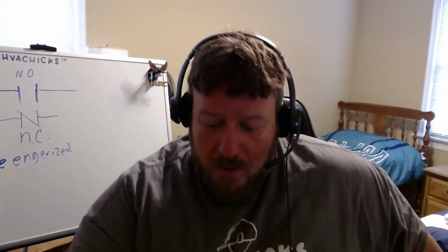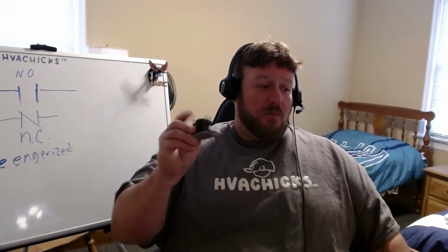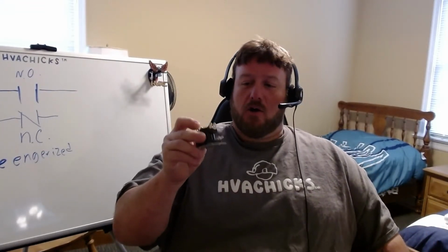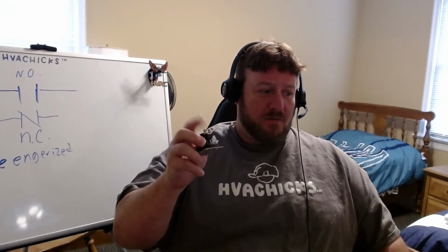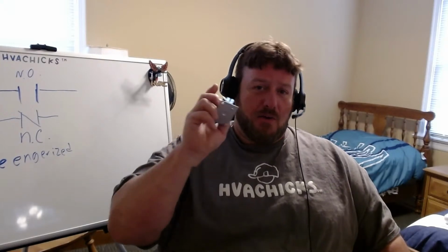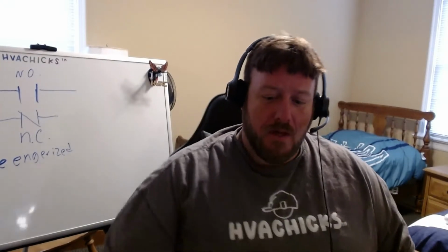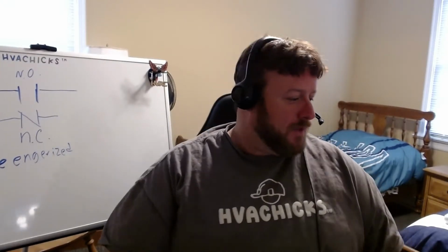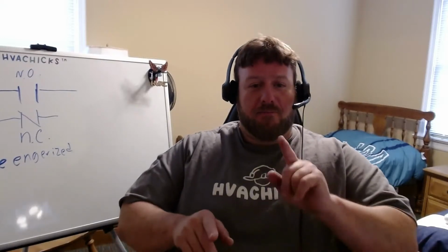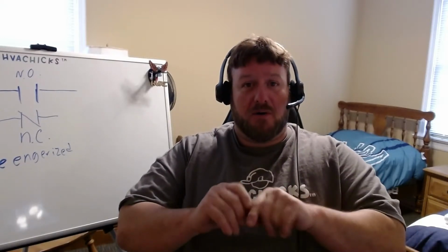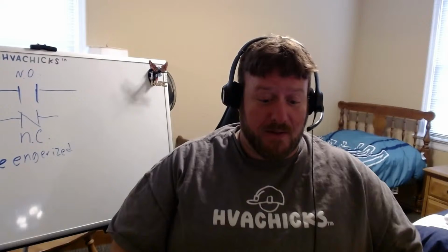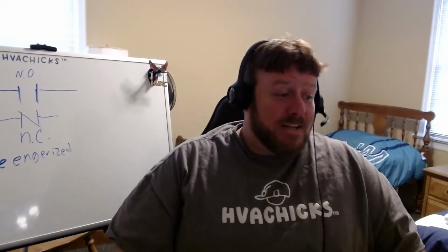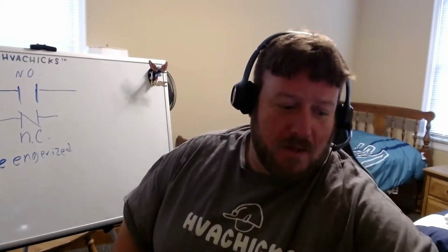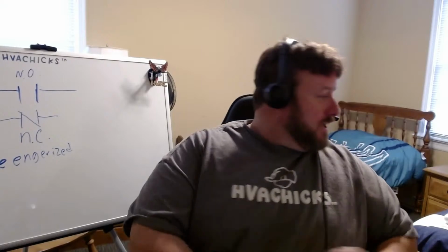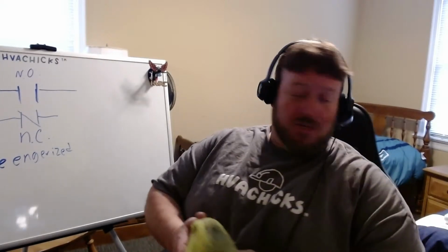Just keep in mind, if power's applied on one side and it's not calling, there is still a possible potential on the other side. You can get hit. A lot of guys don't realize that. I've had meter leads that I've pushed in to check something and it hit something else and went pow and blew off half my lead. It happens. I've replaced more meter leads than I care to in the first few years of doing troubleshooting and diagnostics.